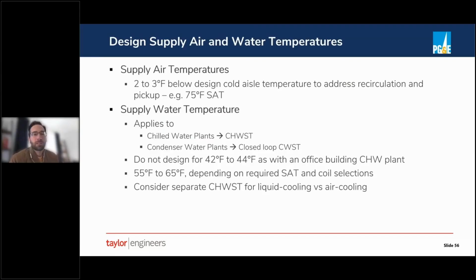Okay, looking at the supply air temperature to the server. So you might think, for instance, that if I'm trying to maintain, as an example, a server entering air temperature of, I don't know, 78 degrees, well, to do that, then my air handling equipment needs to supply air at 78 degrees. But that doesn't account for the fact that there can be some recirculation from the hot aisle to the cold aisle. And there can also just be some thermal pickup across surfaces that are warmer, which can cause some degradation in supply air temperature. So usually what we'll do is select a supply air temperature that's on the order of 2 to 3 degrees less than the temperature that we're trying to maintain within the cold aisle. So again, if I'm trying to maintain 78 in the cold aisle, then I might be designing for 75 degree supply air. Design supply air temperature in turn impacts the design requirements for the chilled water supply temperature that I'm supplying to those air handler coils.